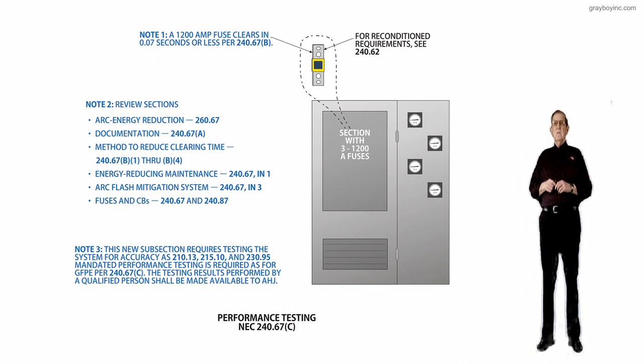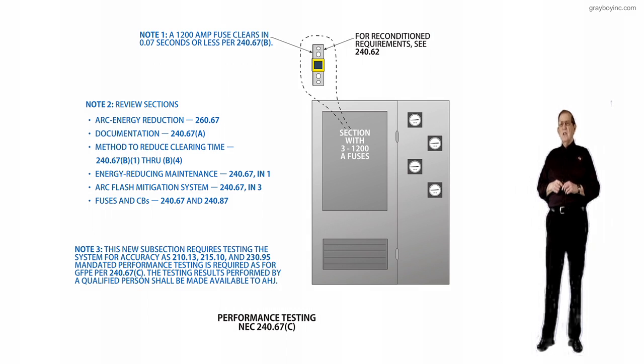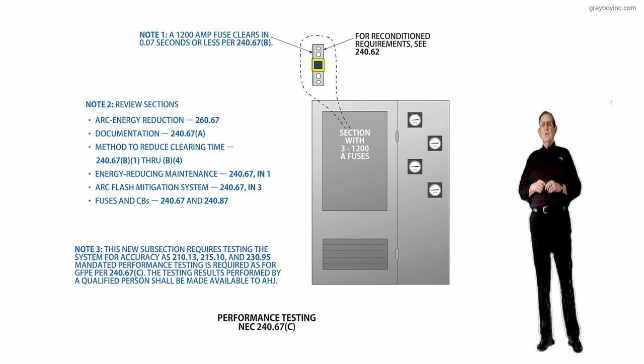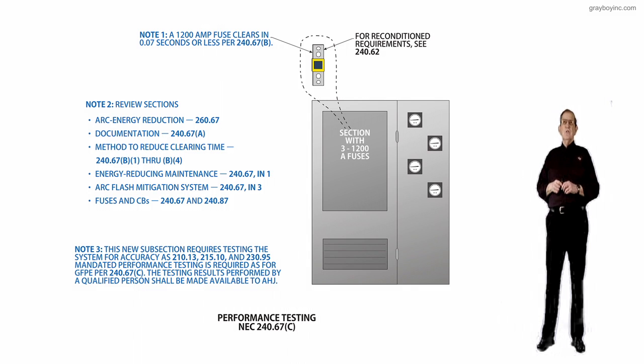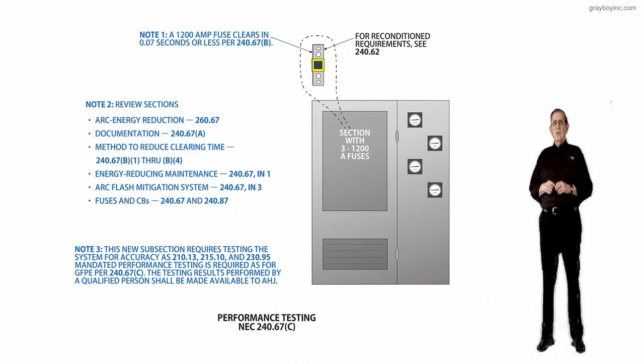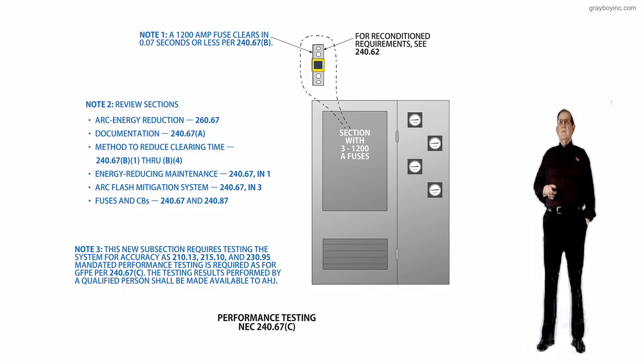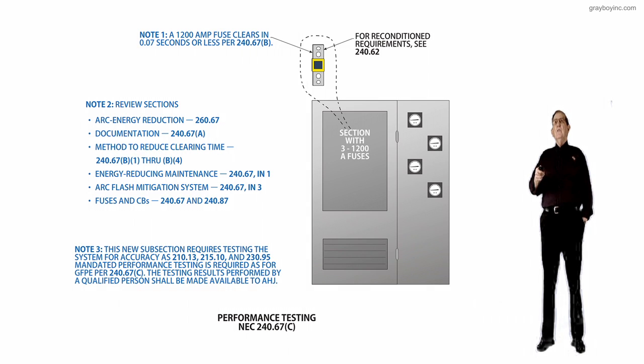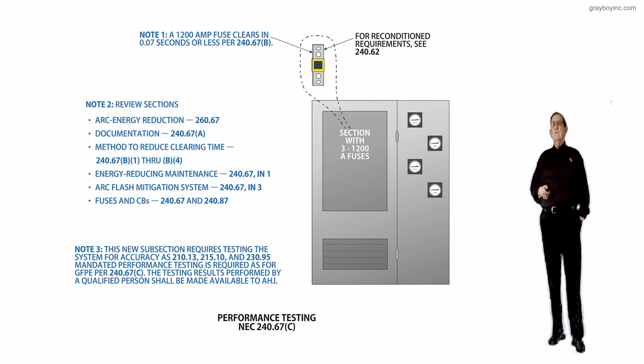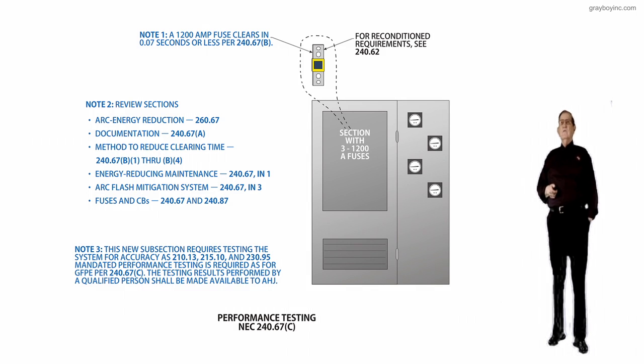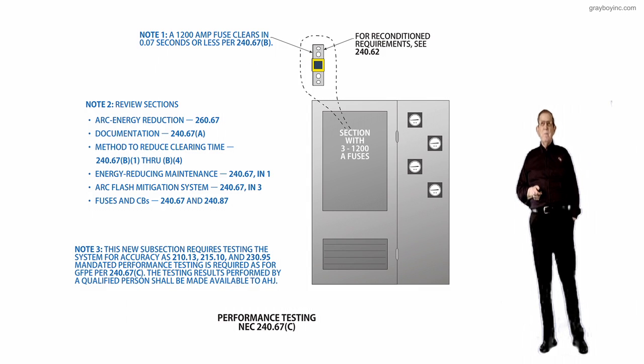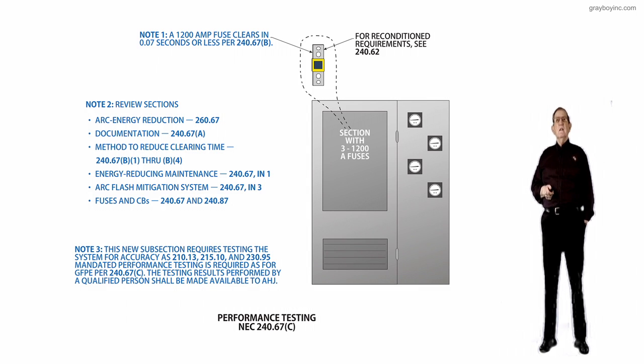Now you can also pick some of this up in 70B, Chapter 17, which will refer you to another chapter to get additional information concerning circuit breakers. But notice if it's fuses, you go to Chapter 18 of 70B. And notice 70E, if you look up here in the table, 110.7 and 130.6(L), as well as (M), also deal with using fuses and other types of equipment to reduce the time limit on current that would feed an electrical arc.